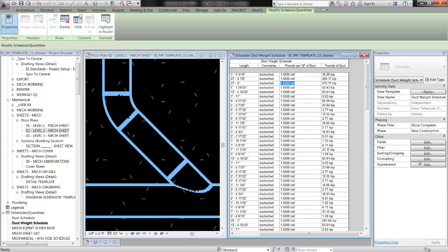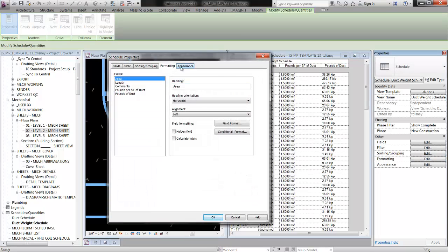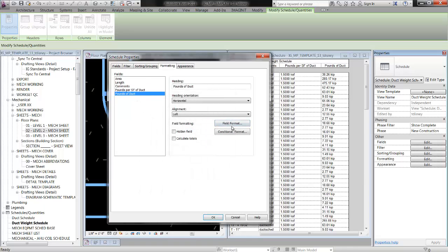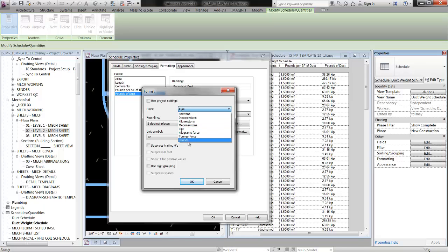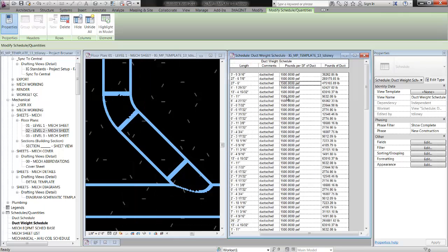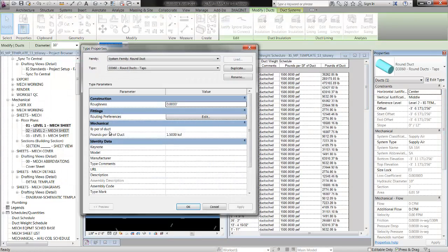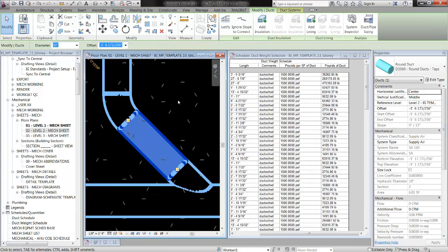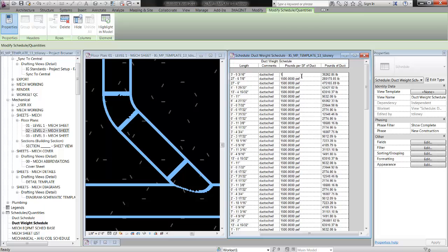Obviously this isn't what I want — I want my schedule to show up in pounds per square foot of duct and pounds of duct. So I'm going to go back into my schedule, go to the formatting tab, select 'pounds per square foot of duct,' and hit the field format button. I'll uncheck 'use project settings' and change the unit to pounds per square foot. Then go back to 'pounds of duct' and field format that to pounds. So I'm just going to enter 1.5 directly from here.